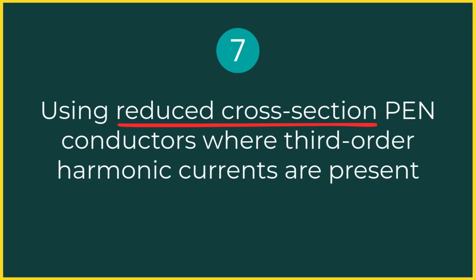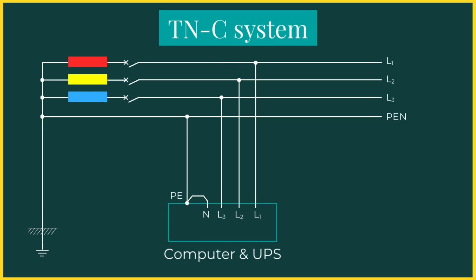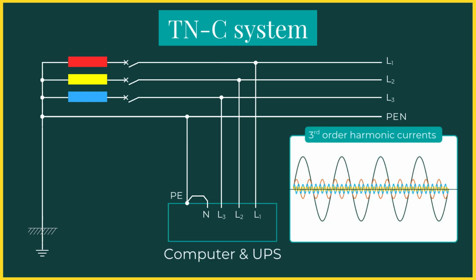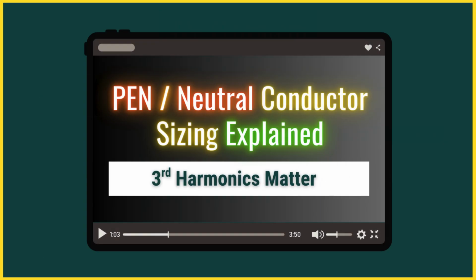Mistake 7. Using reduced cross-section PEN conductors where third-order harmonic currents are present. Modern electronic equipment, such as computers and UPS systems, produces triplen harmonic currents. These harmonics flow in the neutral conductor and add up. In a TNC system, the PEN conductor carries both neutral current and protective current. If the PEN conductor has a reduced cross-section, these harmonic currents can cause overheating and increased fire risk. For this reason, reduced cross-sections for PEN conductors must be avoided. The PEN conductor must always be dimensioned for the expected harmonic current. We will cover the dimensioning of neutral or PEN conductor, considering third-order harmonic currents, in a separate video.